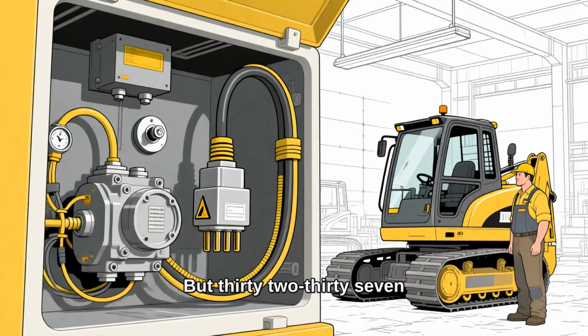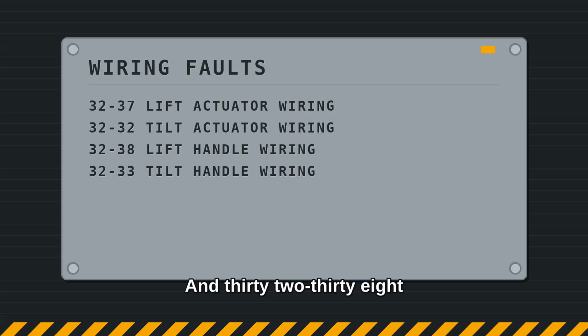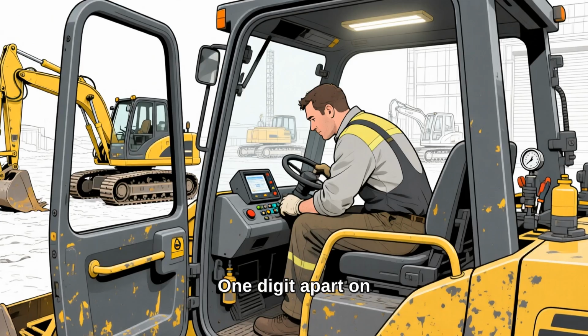But 3237 is lift actuator wiring fault. 3232 is tilt actuator wiring fault. And 3238 is lift handle wiring fault. 3233 is tilt handle wiring fault. All four are wiring, not the part. One digit apart on the display, nowhere near each other on the invoice.